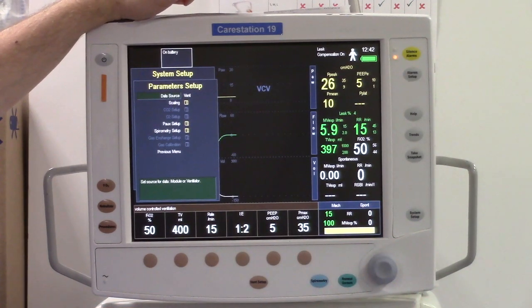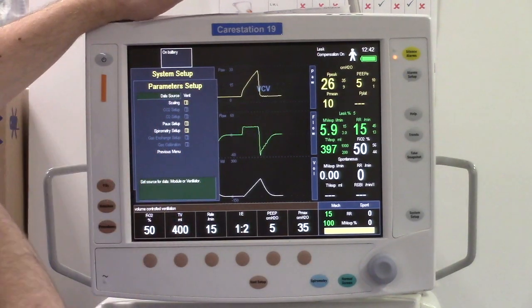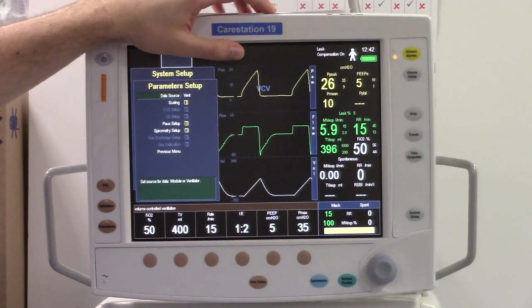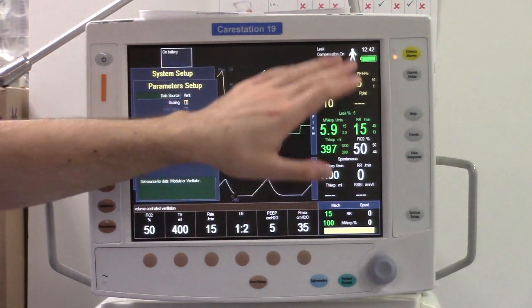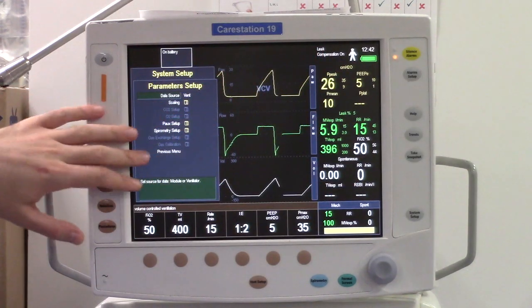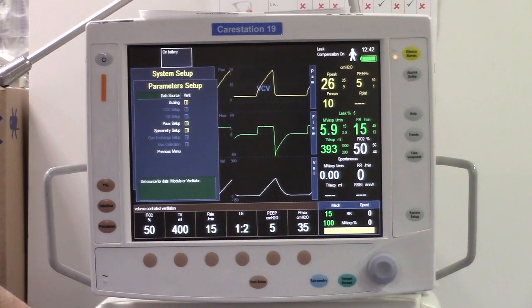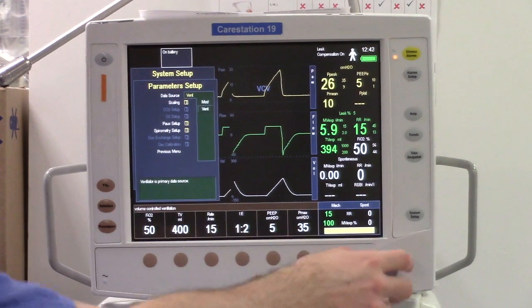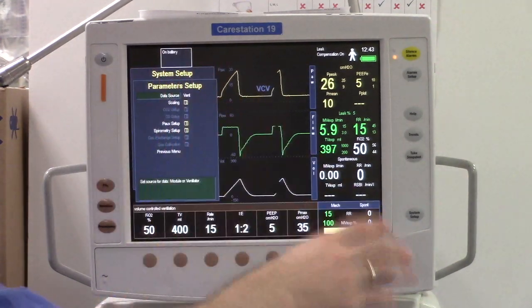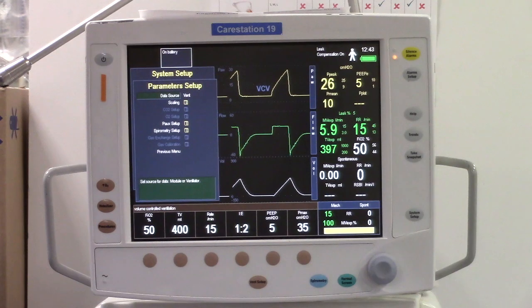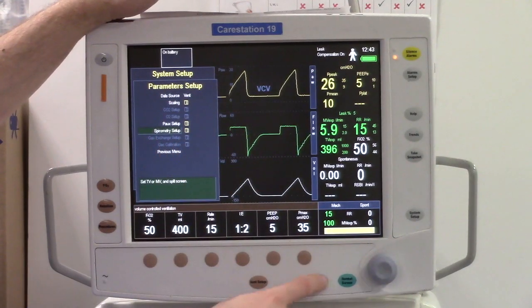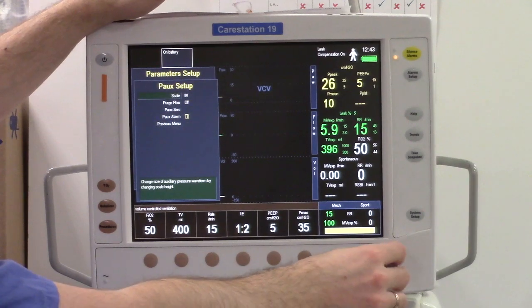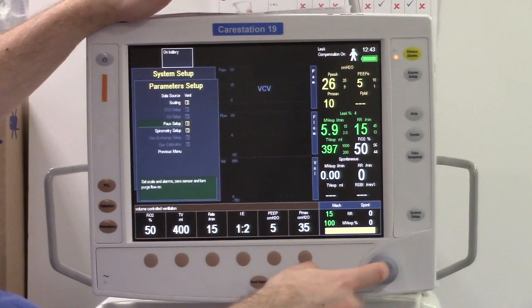Parameter setup. Over here you can select how you want the data to be collected, what's the source of the data. What I mean by data is all these parameters, volume, pressure. Yeah. By default, obviously, it is collected by the ventilator. Yeah. If you have that special module I was talking about, that can be selected as well. So in the option here, you see the module or ventilator. We leave it on ventilator all the time now, as we are using the ventilator. Yeah. Then the rest, we're not using any of these settings unless we're using the spirometry. Yeah. And the Paux setup one here, when we're using that special calorimetry module.